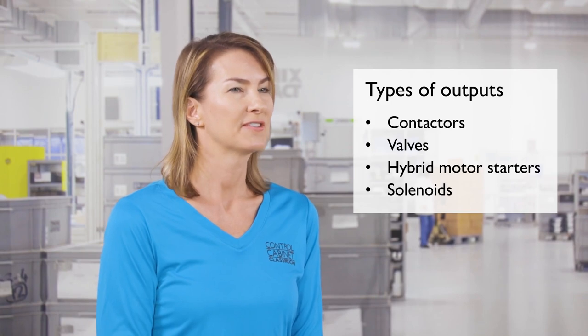Absolutely. Next, let's move on to safe output devices. Outputs are responsible for energizing and de-energizing equipment safely and reliably. These can be contactors, valves, hybrid motor starters, and solenoids, just to name a few. Sometimes it can be difficult or even impossible to have some of these output devices rated for safety. So in many applications, non-safe versions may be used redundantly to achieve proper risk reduction requirements. Advancements in technology have allowed safe outputs like this Contactron Pro hybrid motor starter to be directly connected to safe logic and used as a larger modular safety system.